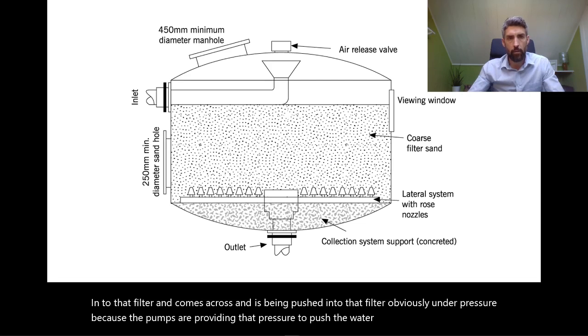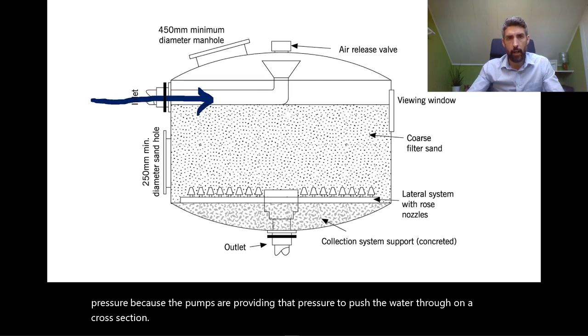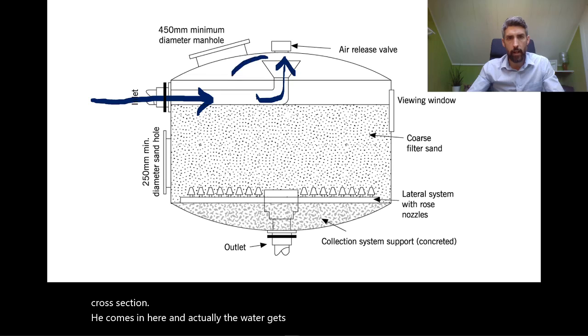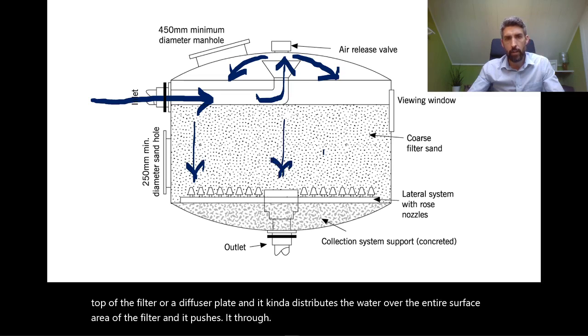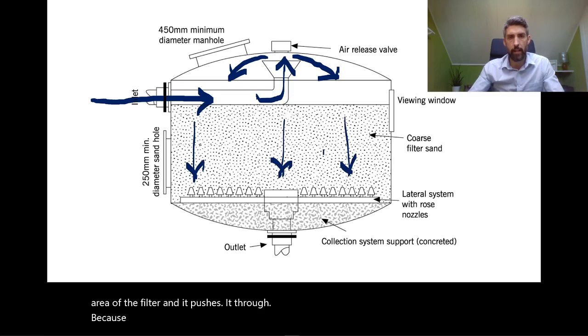On a cross-section it comes in here and the water gets directed upwards, hits the underside of the top of the filter or a diffuser plate, and it distributes the water over the entire surface area of the filter and pushes it through because there's a bed of sand inside the filter.